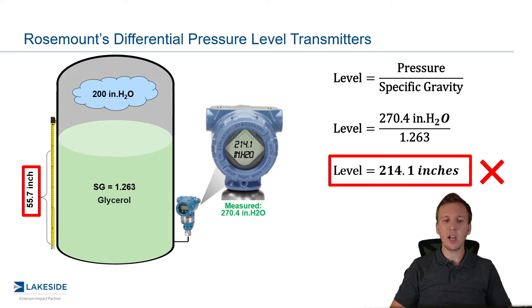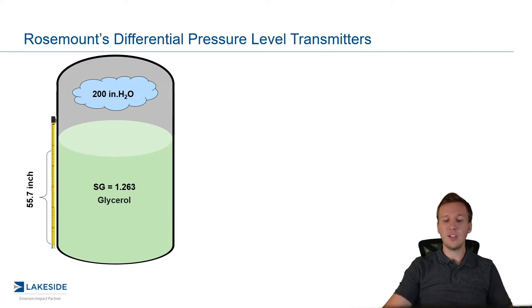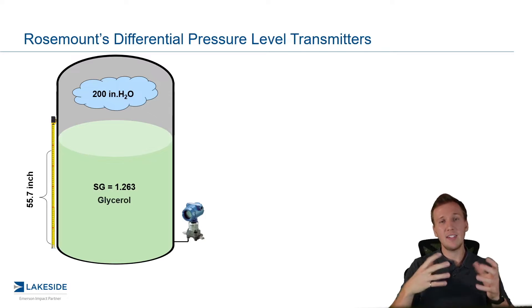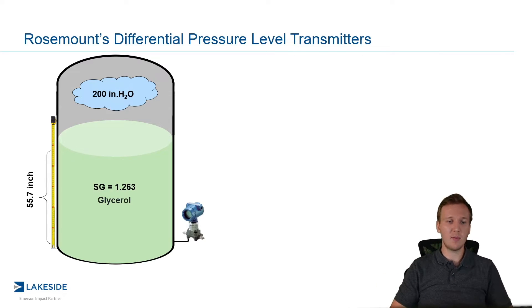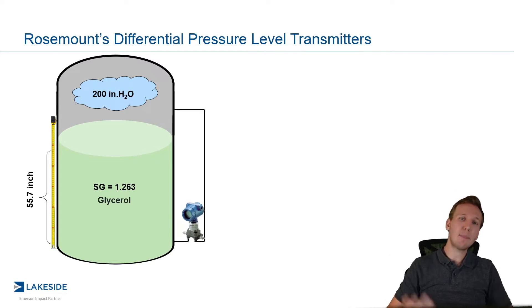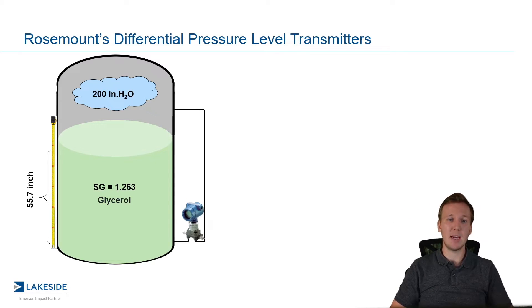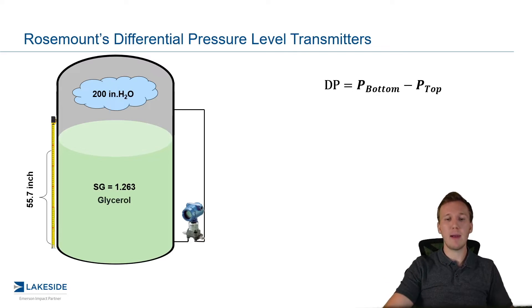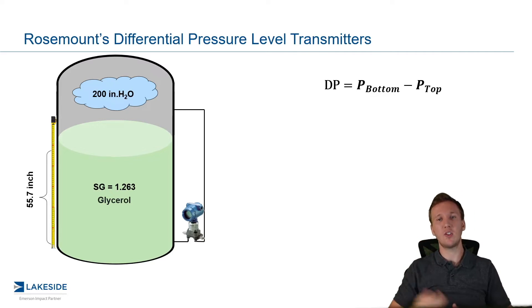So how do we solve this? We instead use a differential pressure level transmitter — and this is where the term DP level comes from. We don't just have it set up as pictured here. Instead, that low side, that low pressure side, we connect it up to the top of the vessel so it can sense that vapor space pressure. Now as the name implies — differential pressure — we are comparing the pressures at the bottom of the vessel versus the top of the vessel.